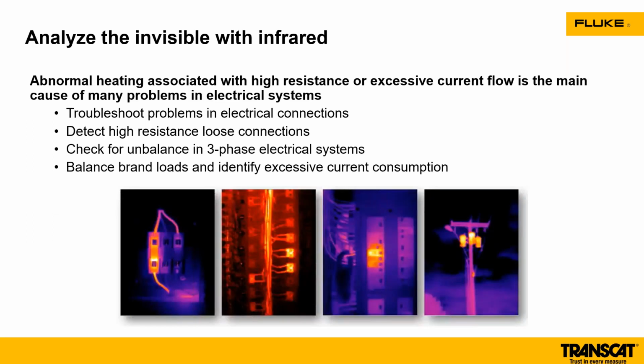As you can see here, some great examples of situations where we can see excessive heat. We're troubleshooting problems on the electrical side. Maybe we're checking if there's an unbalance on a three-phase system. We can easily see where that's happening. You can see loads on a panel, and on this one the third one from the left is causing a problem. Even the heat on your transformers, seeing where those potentially could fail. A key win on this, and again, keeping you safely out of that situation.